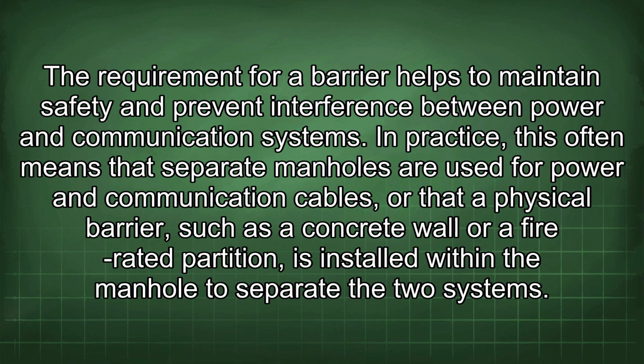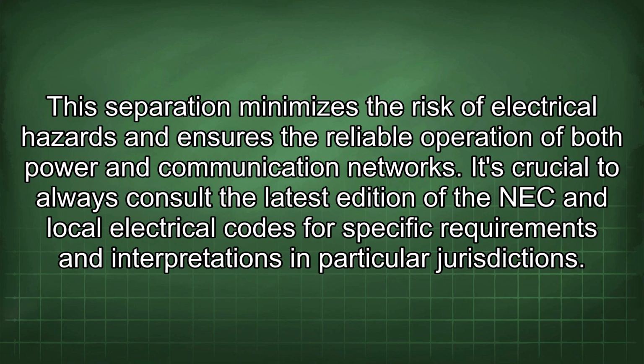In practice, this often means that separate manholes are used for power and communication cables, or that a physical barrier, such as a concrete wall or a fire-rated partition, is installed within the manhole to separate the two systems. This separation minimizes the risk of electrical hazards and ensures the reliable operation of both power and communication networks.